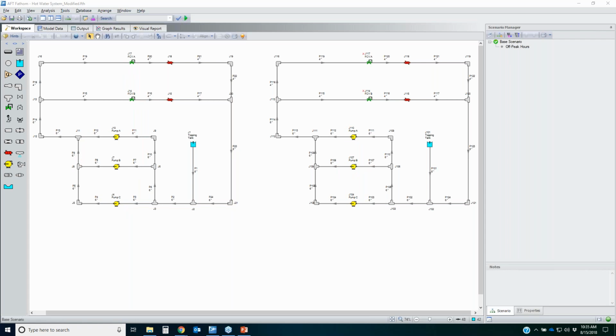I'm not going to run this scenario because the system and the pumps were designed to meet the peak hour flow rates, okay? And so the energy costs by using VSDs versus control valves, fairly small. You'll see exactly what those costs are here in a minute. So I'm going to focus on the off-peak hour scenario.